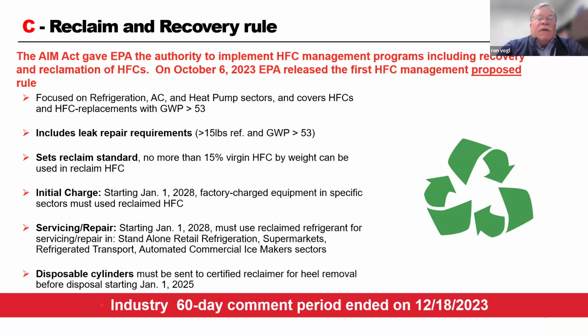They're trying to set a reclaim standard that you cannot have more than 15% of virgin refrigerant in used reclaim, which is often done by the reclaimers. They bring things back and then they reconstitute the blend by using some virgin refrigerant. They're going to be restricted there. In 2028, some equipment that's factory built will have to use reclaimed HFC. The issue there is the industry doesn't know if there's going to be enough, especially if you get into lower GWP products, to satisfy that. For service and repair in 2028, you must use reclaimed refrigerant for service in standalone supermarkets, refrigerated transport, et cetera, et cetera. Again, the industry is pushing back because they don't believe that there is enough reclaimed refrigerant to satisfy that requirement.